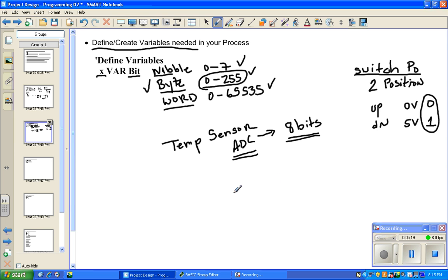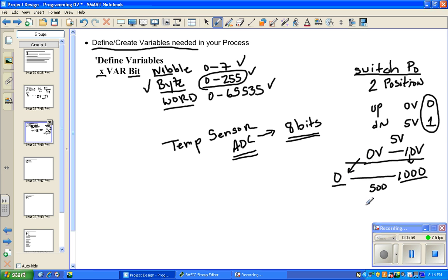And also for analog information, there's a direct correlation between the voltage and the number. 0 to 10 volts represents 0 to 1000 in the PLC LOGO, which means if you are receiving 5 volts, you would receive 500. If you receive 10 volts, then the LOGO would read it as 1000. If the voltage is 0 volts, then the LOGO will read it as 0.